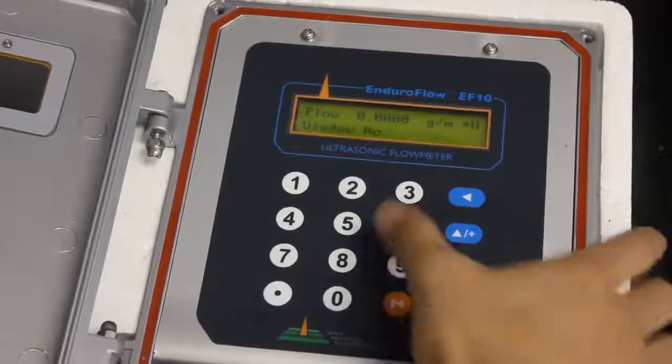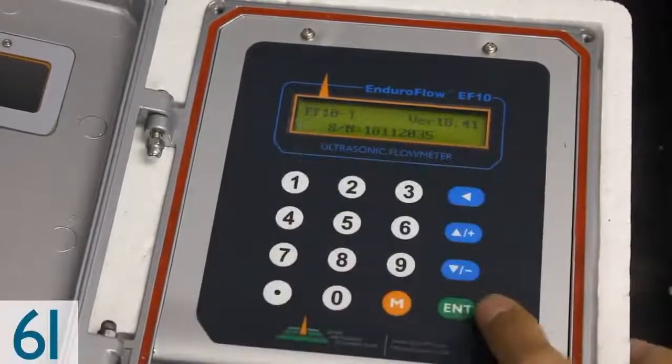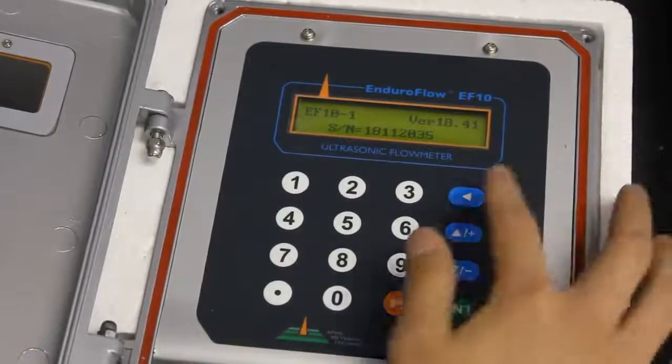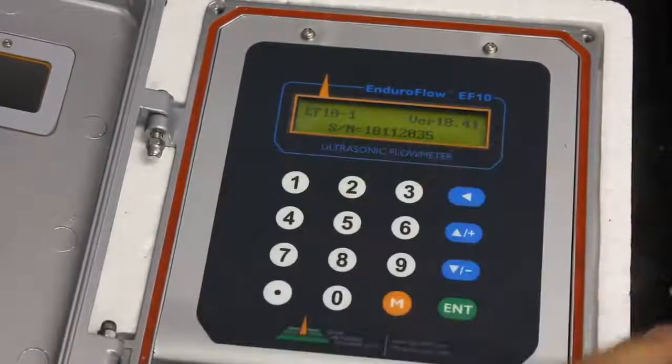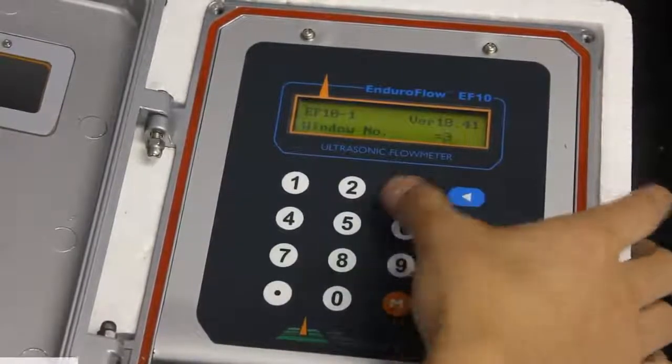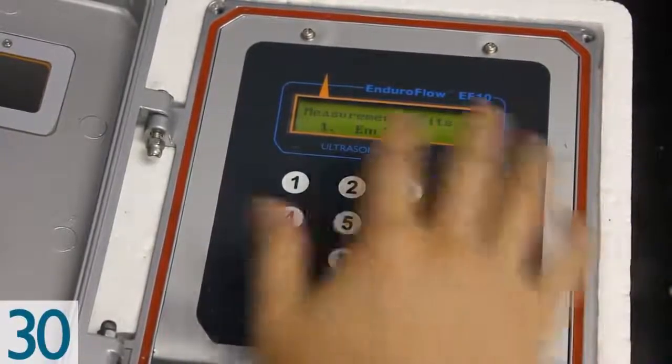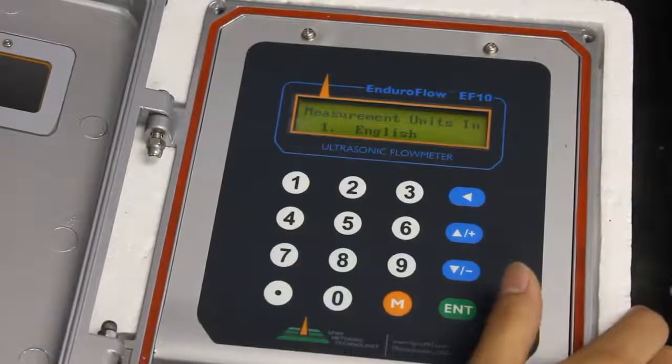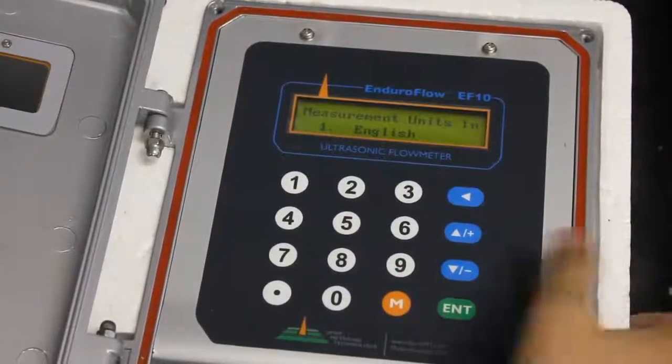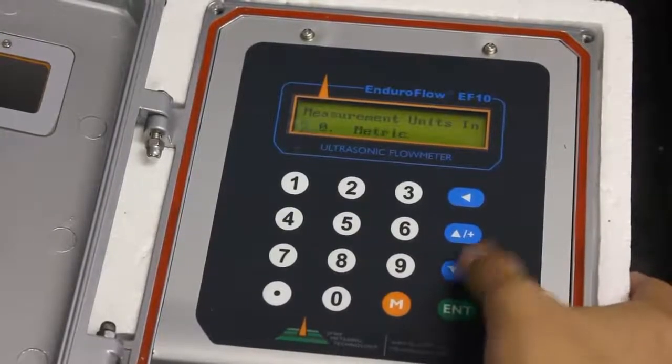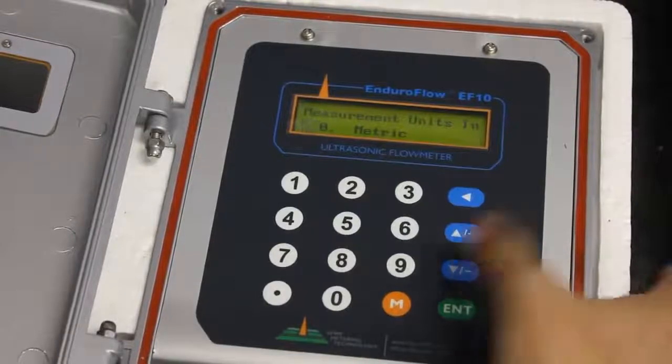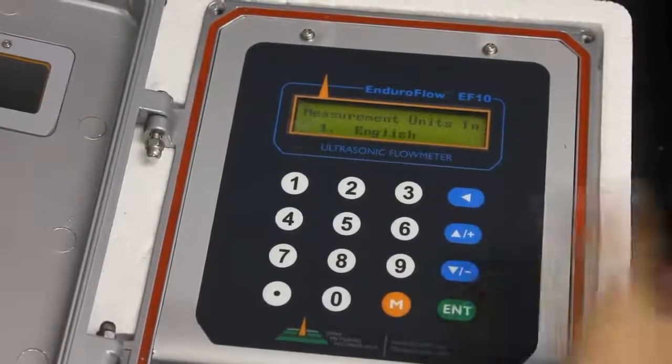First we need to go to menu 61 to check and make sure we have the correct version, the correct serial number, and the correct model, the EF-10. Next we go to menu 30 to set the measurement unit. It's already in English which is the factory standard, but if you wanted to change that you would just press enter and scroll down or up to change between English and metric.